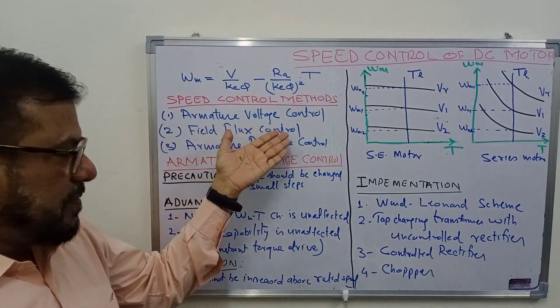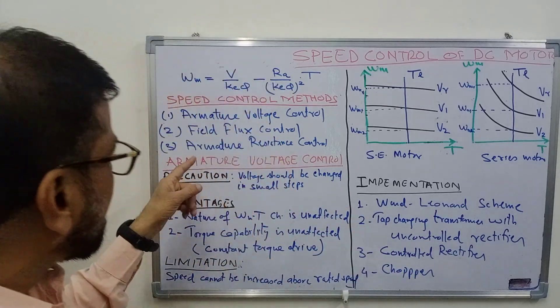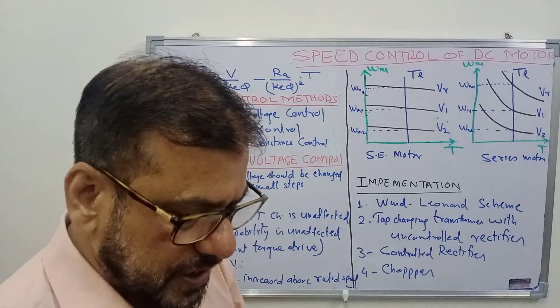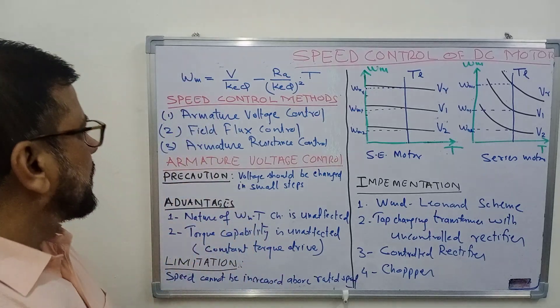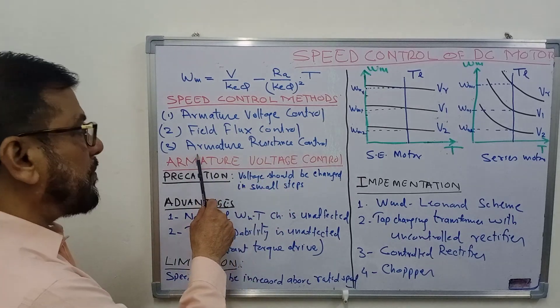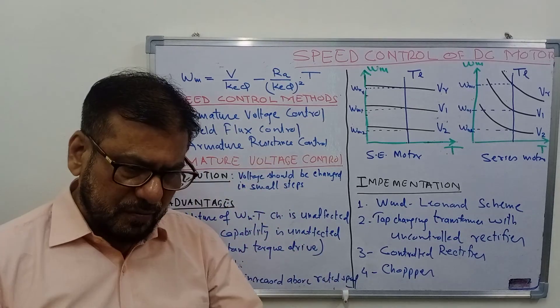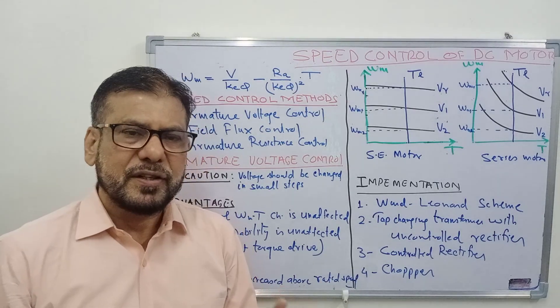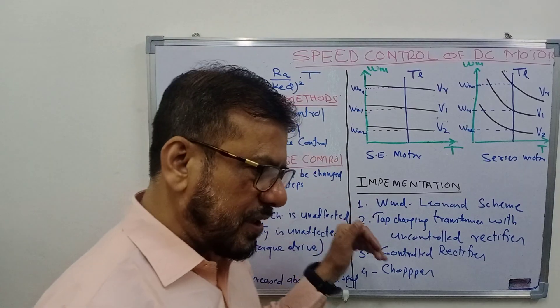The first is armature voltage control, where we change the voltage applied across the armature. The second method is field control or field flux control, where we vary the flux produced by the field winding by varying the current through it. The third method is to vary the resistance of the armature circuit by inserting external resistance in series with the armature.